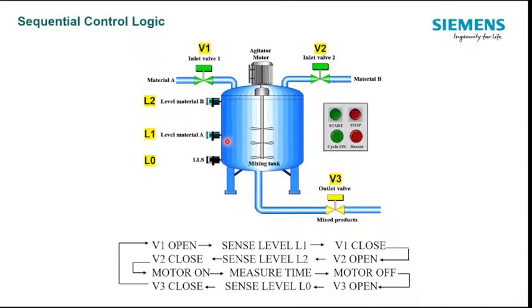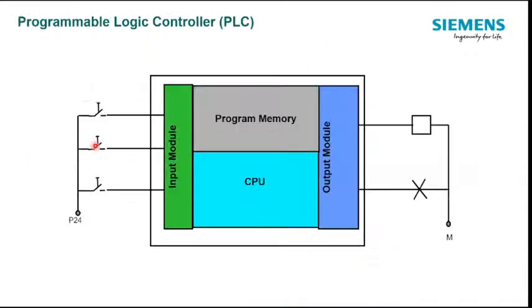Once it reaches the level L1, there I have a limit switch whose NO contact will change over. That limit switch NO I will take as another input. So as soon as material A reaches level 1, this NO will be closed and the circuit will be closed. I will get a positive 24 volt at this input terminal, which will be sensed by the CPU as a signal that level 1 has been reached.